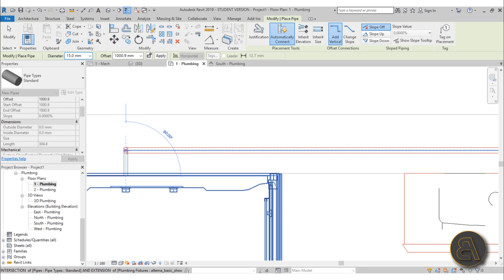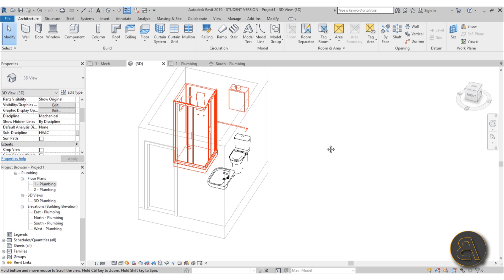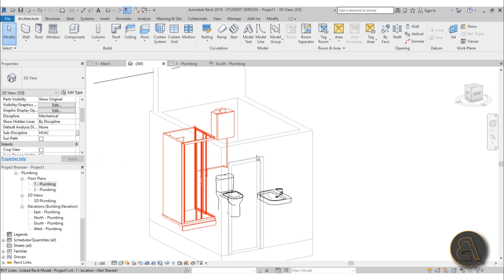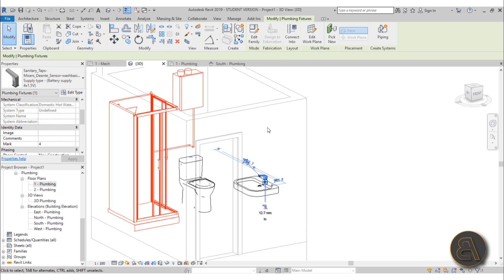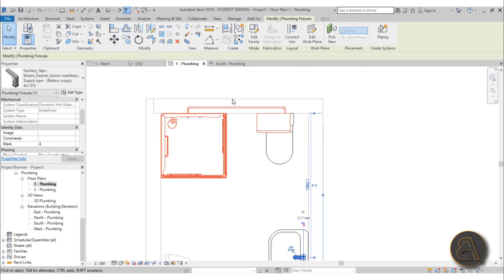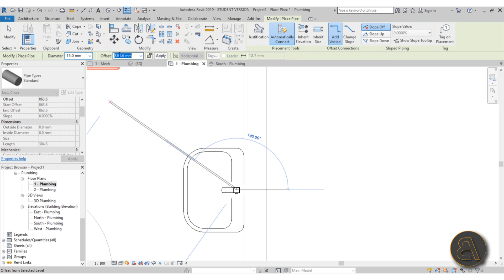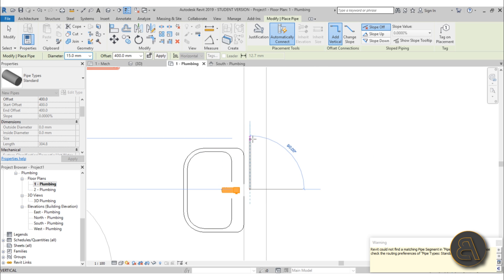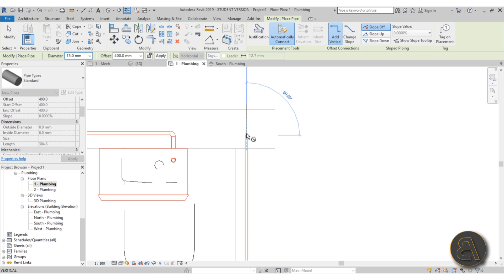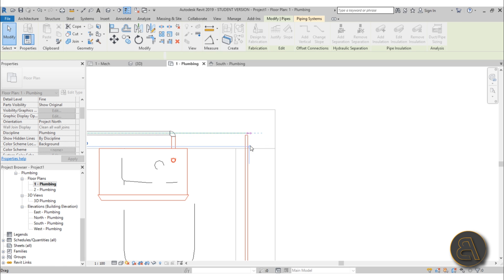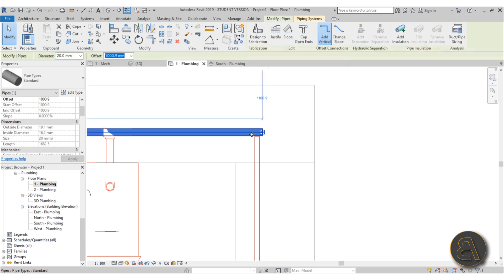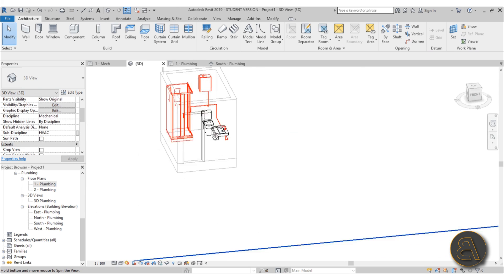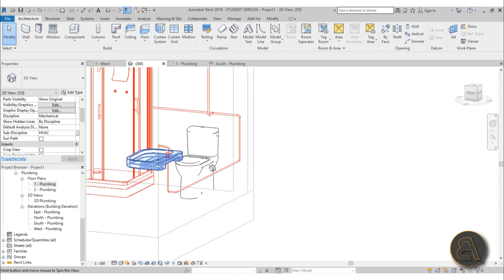Select the shower's hot water inlet and extend the pipe at the same offset level of 1000 millimeters to connect them. In 3D view, the hot water is now connected to the shower — everything lights up in red to confirm proper connection. Now let's connect hot water to the sink: give it an offset of about 400 millimeters since it's below the sink, run it into the wall and extend it to connect. In 3D, the hot water is automatically connecting.